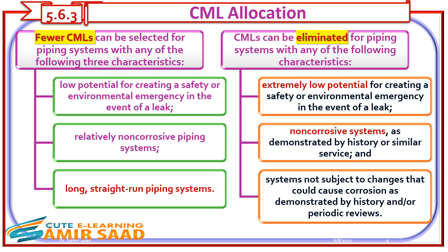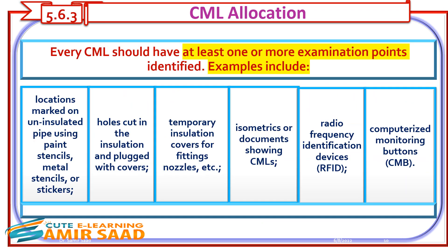CMLs can be eliminated for piping systems with any of the following characteristics: extremely low potential for creating a safety or environmental emergency in the event of a leak; non-corrosive systems as demonstrated by history or similar service; and systems not subject to changes that could cause corrosion as demonstrated by history and/or periodic reviews. Every CML should have at least one or more examination points identified.